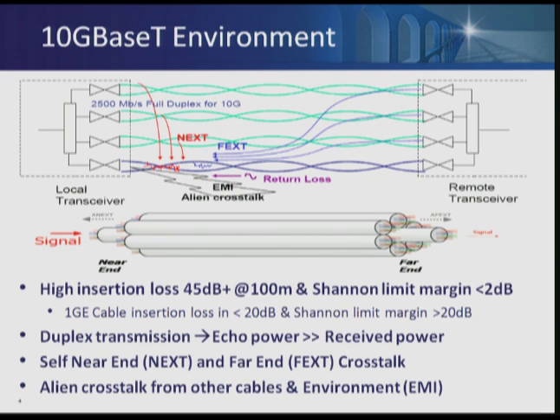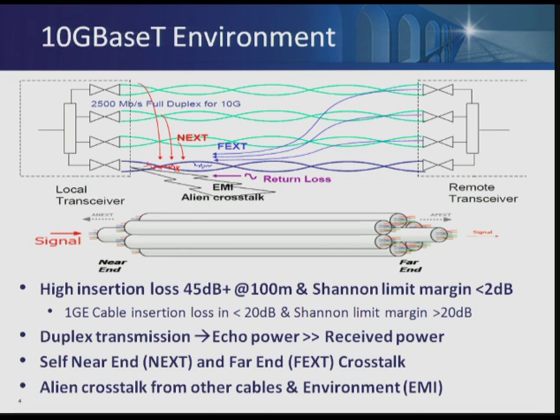In a typical data center application where wires are pulled in a six-around-one configuration, there could be a scenario where you have a victim cable and six aggressors. All of these aggressors are inducing alien NEXT on top of the victim cable. All of these impairments have to be taken into account for a proper design of 10G Base-T to operate at 100 meters.